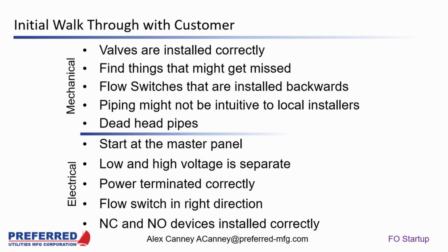I look at, like I said earlier, flow switches, making sure a flow switch is in the right direction so it works properly. Any motorized ball valves, making sure that they're installed correctly, that the wiring is complete. You've got level switches on the day tanks, making sure they're installed correctly. Wire floats or any type of other level sensing devices on a storage tank, making sure that that's installed correctly, making sure the wiring's complete, that the low voltage wiring for that is not running in AC conduit.